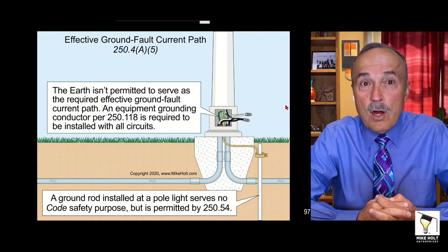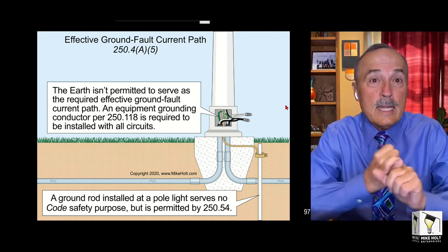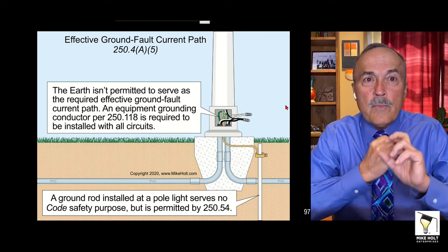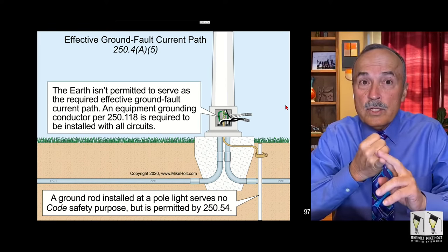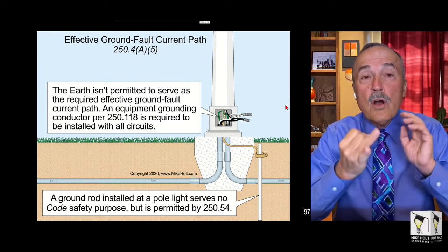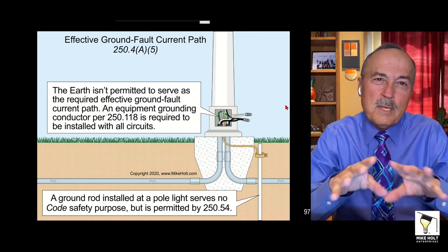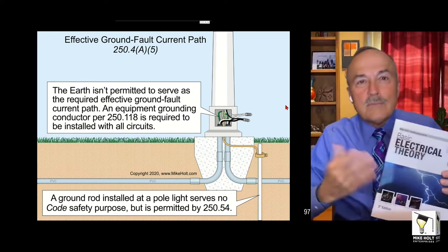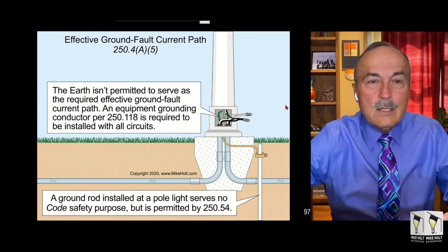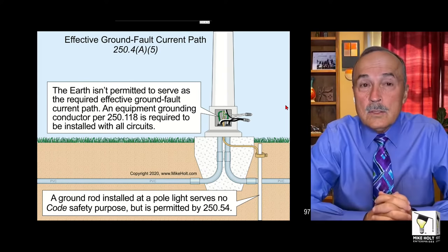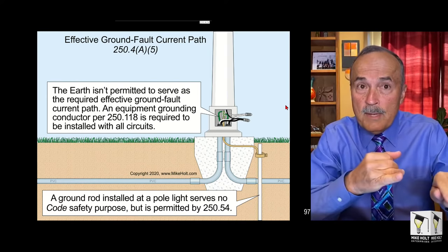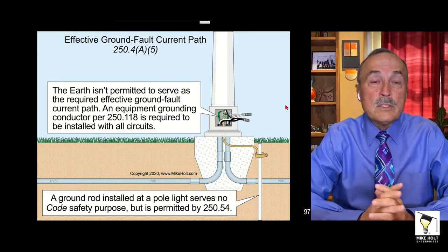I equals E over R. E is electromotive force - we use the word voltage to measure that. I equals E (the voltage) over R (the resistance), or really the impedance in AC circuits. So if you have a low impedance effective ground fault current path, what happens? You trip the breaker.